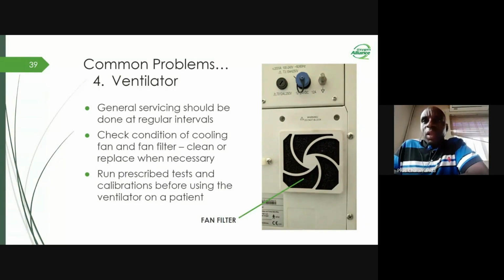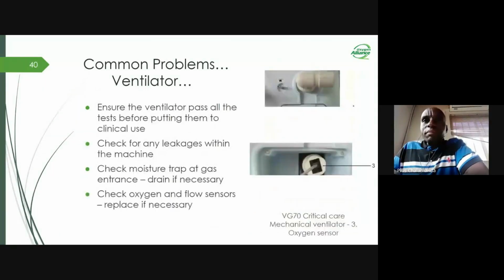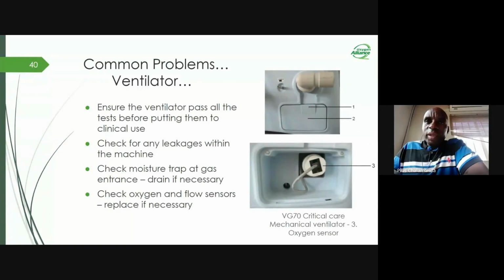Run prescribed tests and calibrations before using a ventilator on a patient. This is usually done by the anesthetist running the calibration tests on the ventilator. This is very necessary, and they have to make sure, or you have to make sure, that the machine passes all the tests that are run on the machine. Because if it fails one of the calibration tests, it means the ventilator is not good to be used on the patient. Check for any leakages within the machine. Check the moisture trap at the back of the machine and clean if necessary.